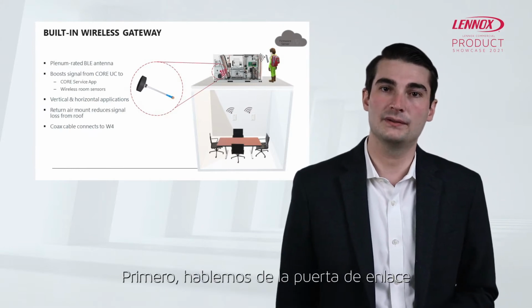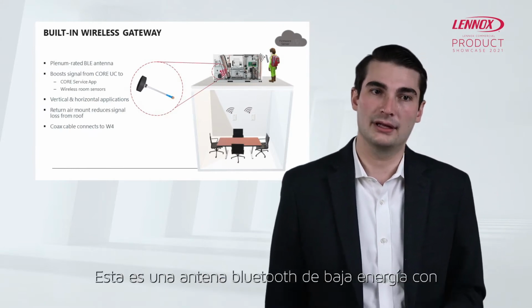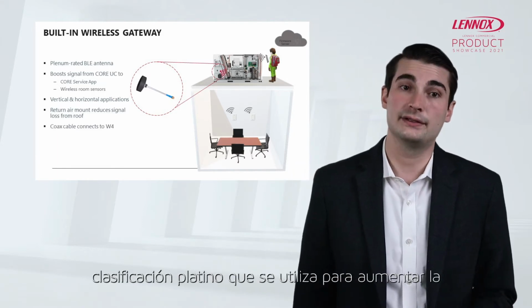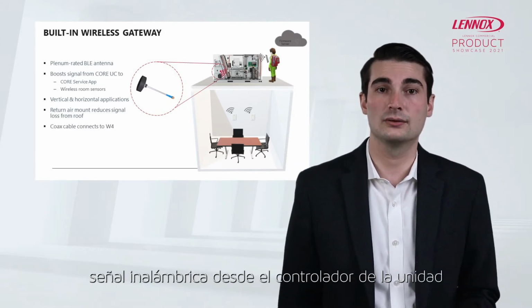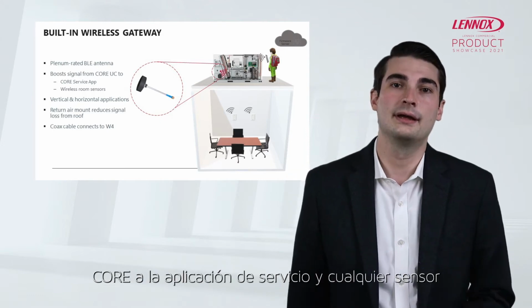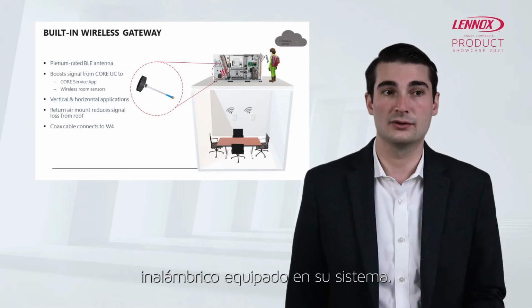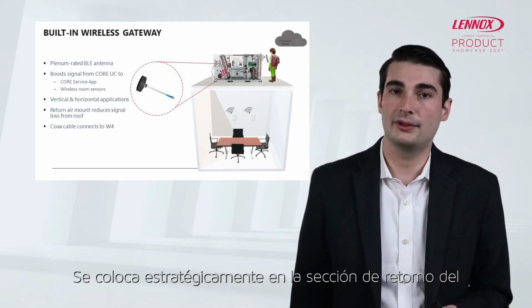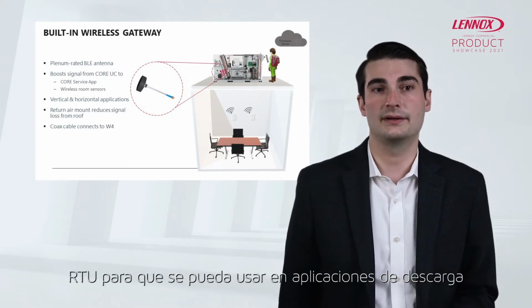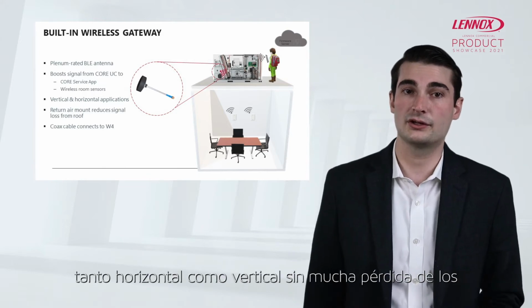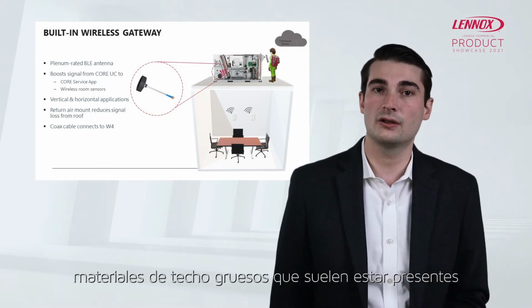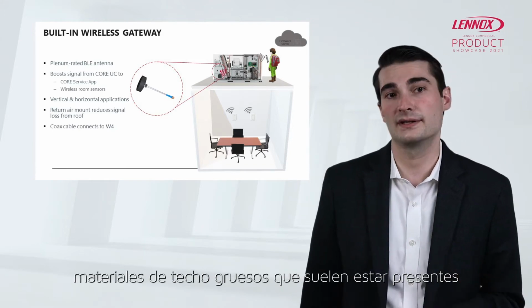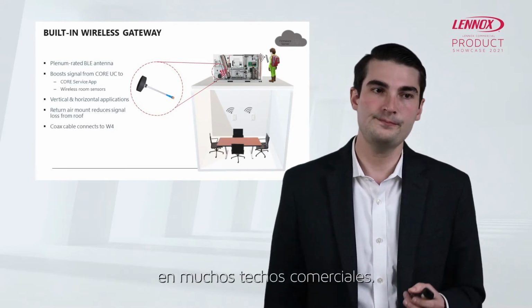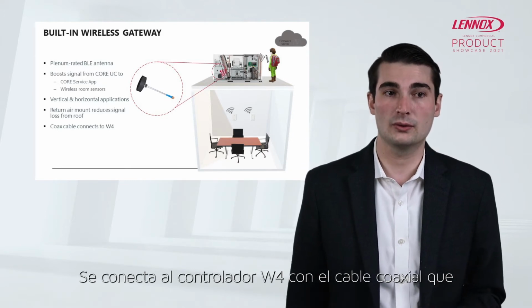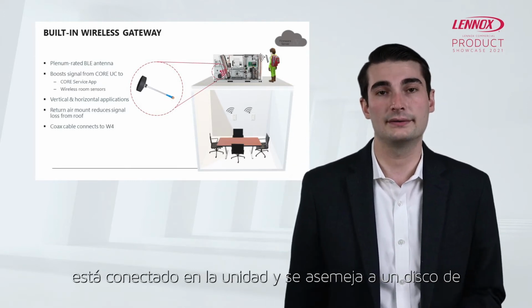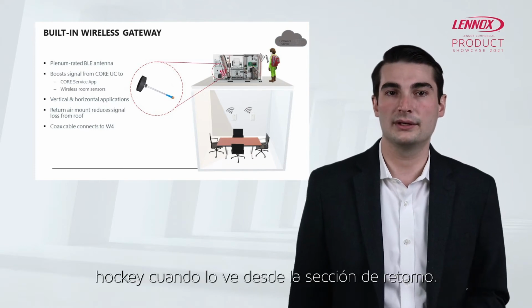First, let's talk about the built-in wireless gateway. This is a plenum-rated Bluetooth low-energy antenna that boosts the wireless signal from the core unit controller to both the service app and any equipped wireless sensors in your system. It's strategically placed in the return section of the RTU so it can be used in both horizontal and vertical discharge applications without too much loss from the thick roofing materials typically present in commercial roofs. It connects to the W4 controller with a coaxial cable wired in the RTU, and resembles a hockey puck when viewing it from the return section.